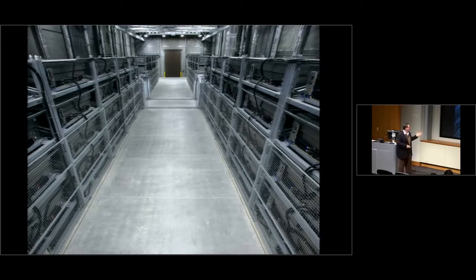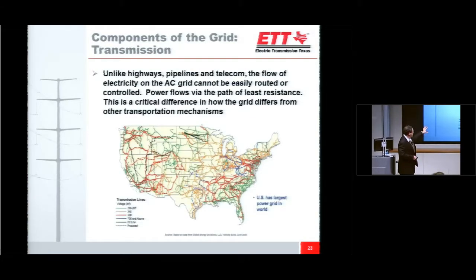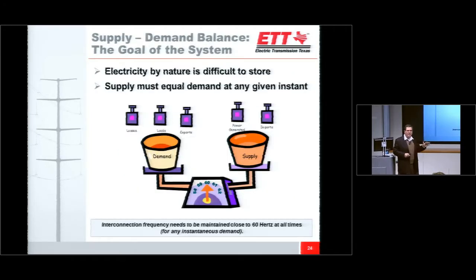So you can imagine the battery technology it would take to serve a city like Austin or even Dallas. Batteries are not there yet, so this grid has to be managed such that demand and supply are equal at all times. We have dispatchers who work round the clock 24 hours, and their job is, if the frequency goes from 60 hertz to 59.9 or 60.1, to adjust by bringing a generator up or down to keep it at 60 hertz. They have 4 seconds to make those adjustments. Those dispatchers are in control rooms with computers, constantly moving our system up and down to maintain demand and supply. That's what's done in the Eastern Interconnect, the Western Interconnect, and ERCOT.